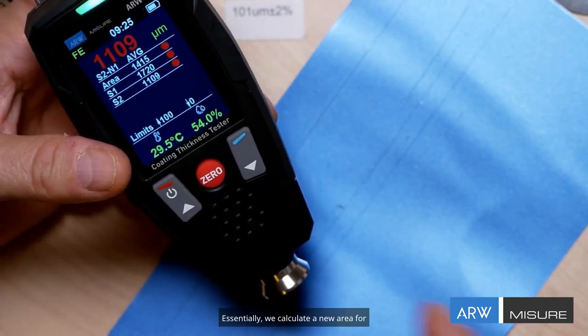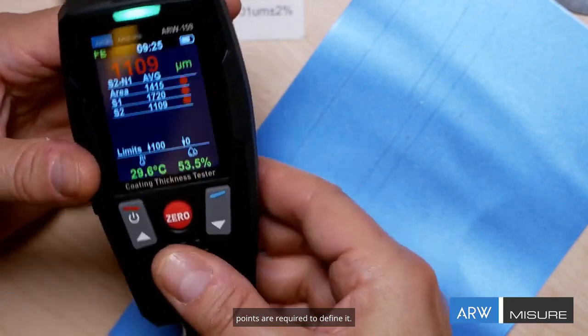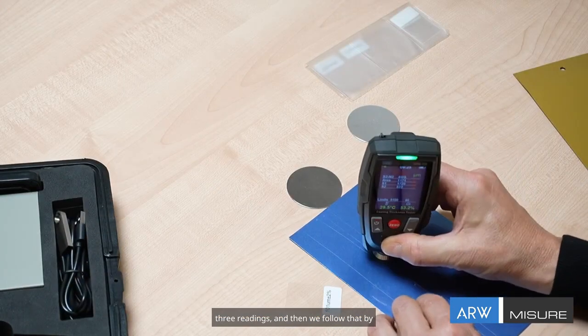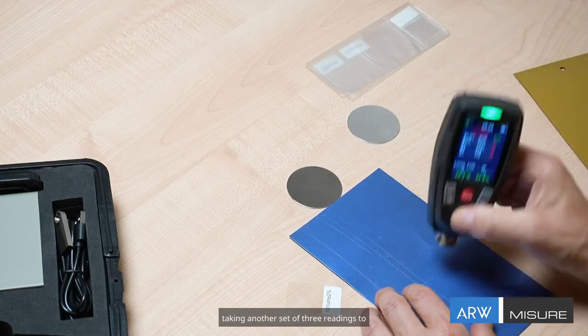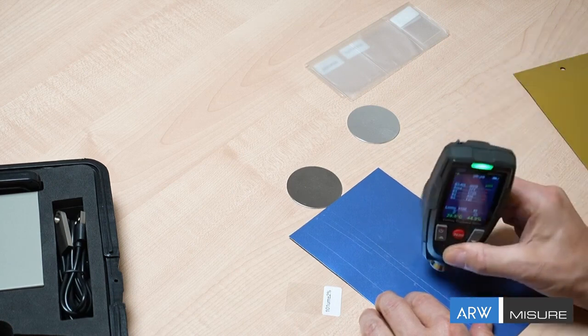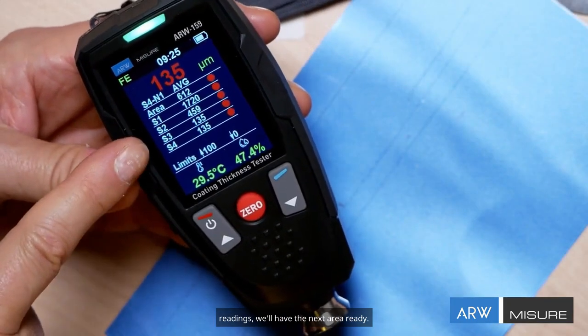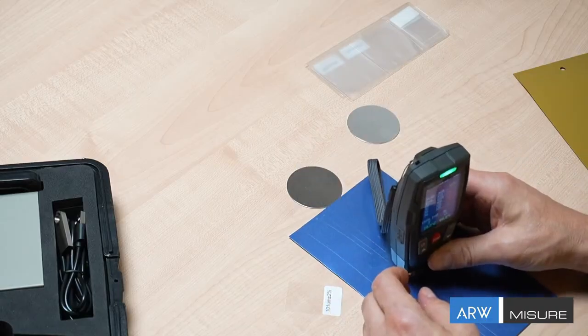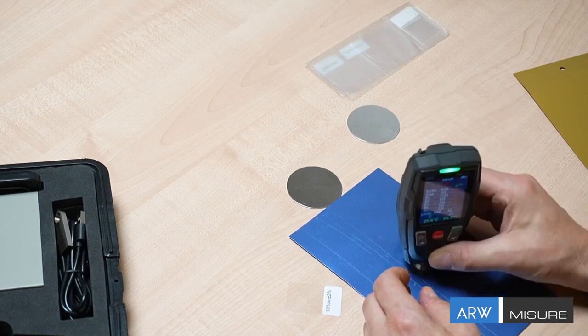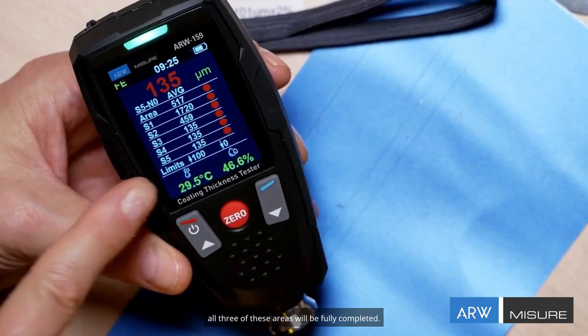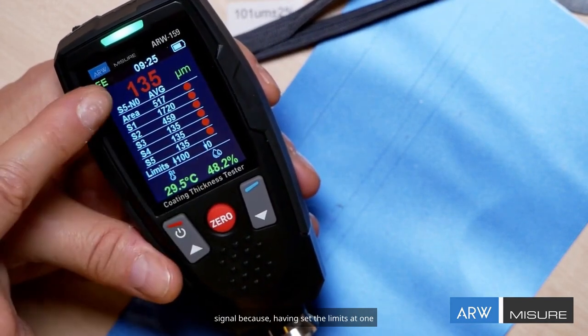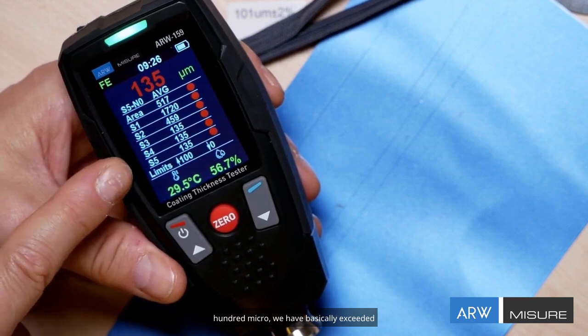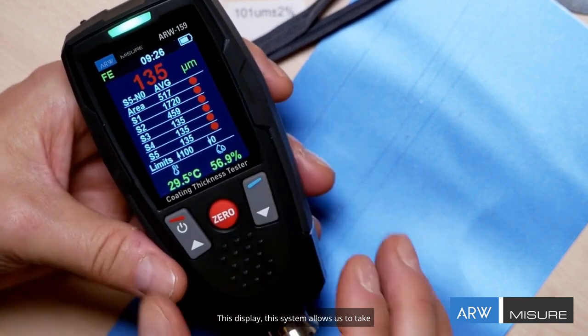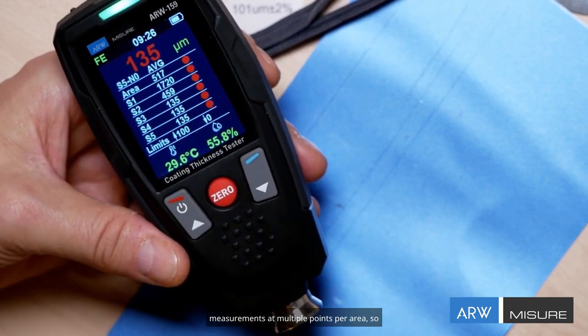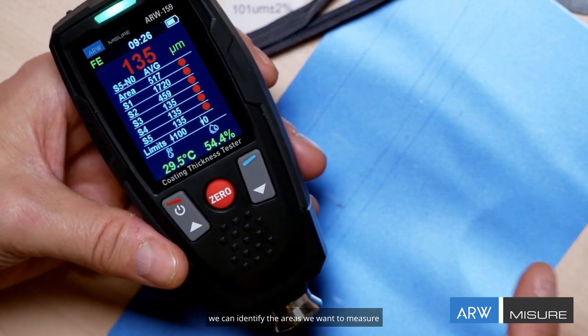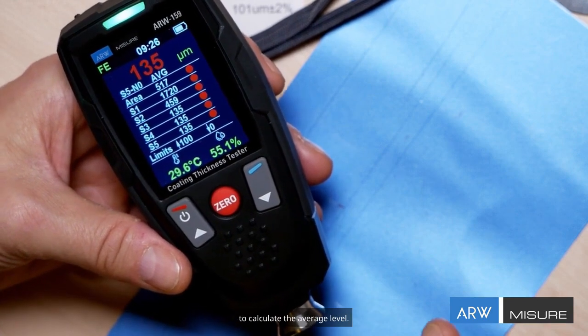Essentially, we calculate a new area for every 3 readings we collect, since 3 points are required to define it. In this scenario, we first take a set of 3 readings, and then we follow that by taking another set of 3 readings to continue the sequence. And every single time we take 3 data readings, we'll have the next area ready. If we complete the measurement, as soon as we have finished the measurement, all 3 of these areas will be fully completed. In this case, we are seeing a red warning signal because, having set the limits at 100 micro, we have basically exceeded those established limits. This system allows us to take measurements at multiple points per area, so we can identify the areas we want to measure and set the points per area on which we want to calculate the average level.